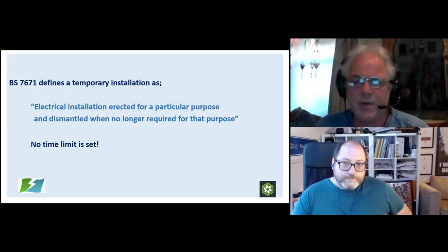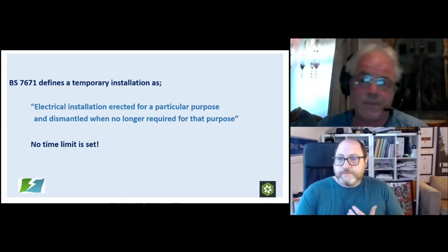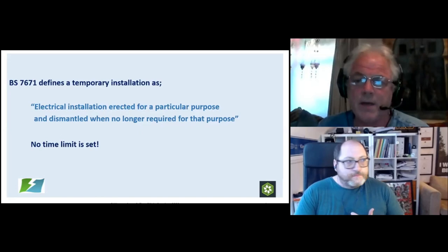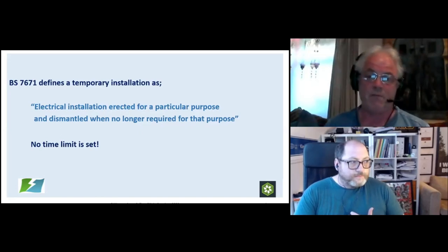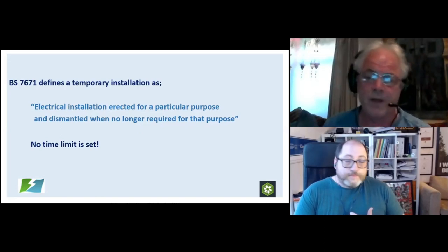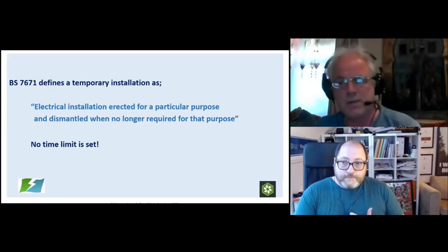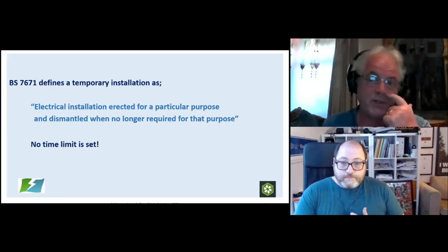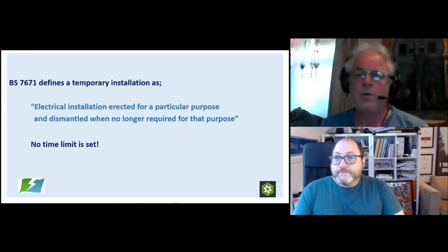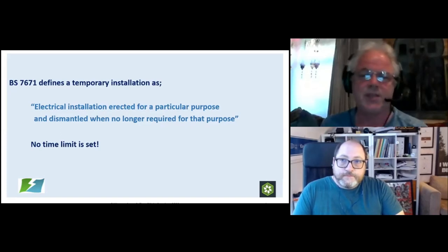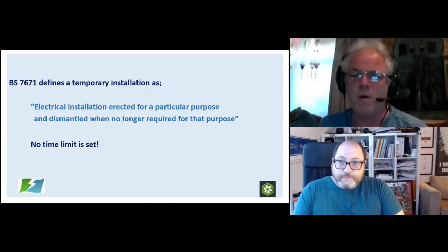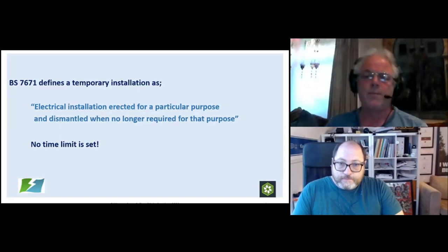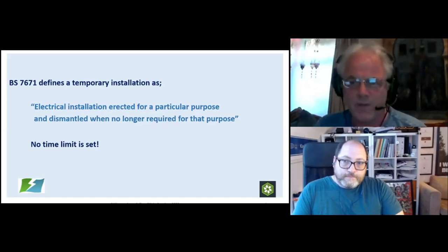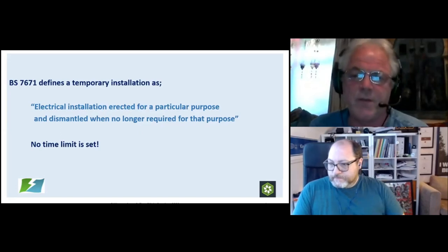You may have a system like we do with some of the events we go to, where they put a system in in April and it comes out in October. So what do we do about that? Well, it's a temporary system. We install it to BS7671 and BS7909. We do the inspection and testing to BS7909. But what we will do is go back and re-inspect after a certain amount of time.